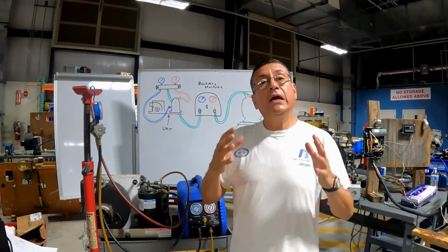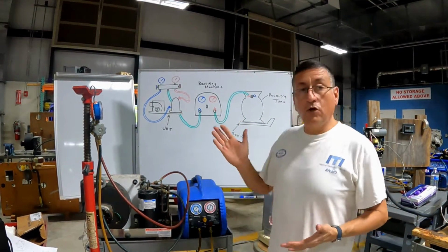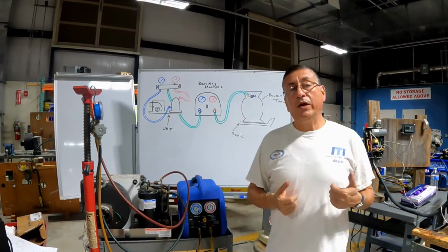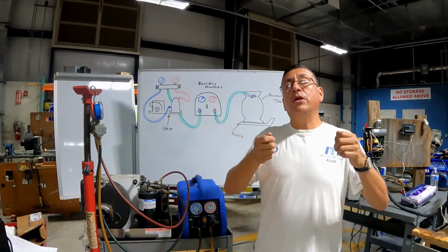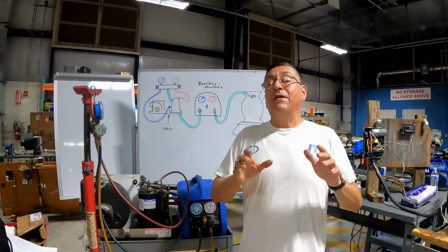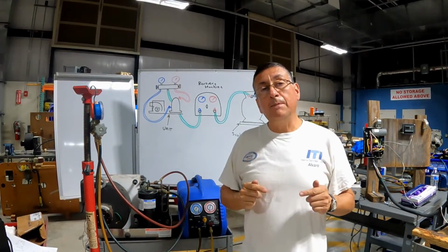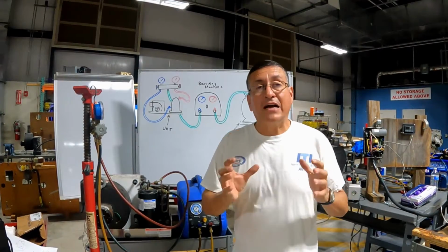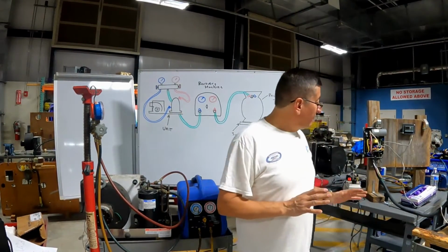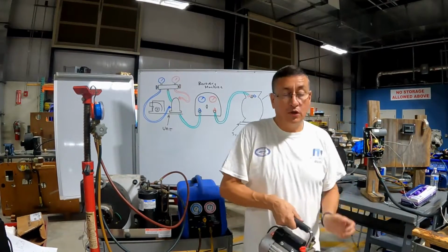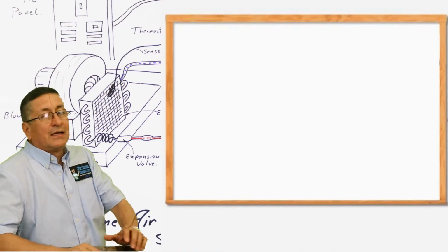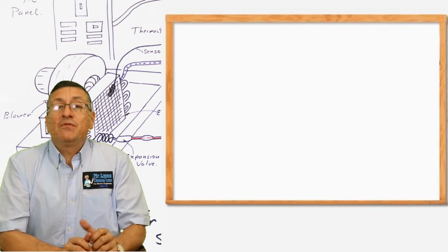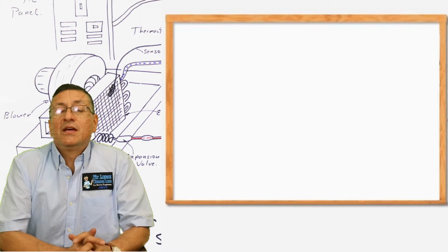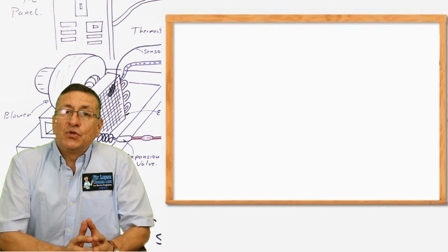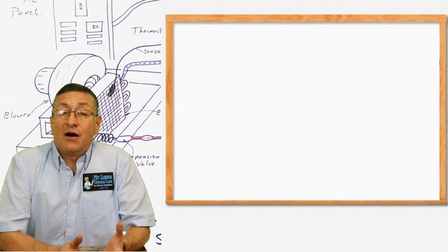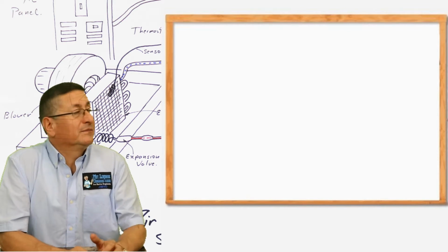Okay, right now we can start with the reparation. We can remove the compressor, remove the evaporator, we can replace the unit, and we can put back the lines, and before we recharge the system, we are going to do the vacuum. The vacuum procedure, in the vacuum procedure, we are going to use the vacuum pump. And now, in the same equipment, in the self-contained unit, we are going to analyze the procedure and how to do the vacuum in that equipment.